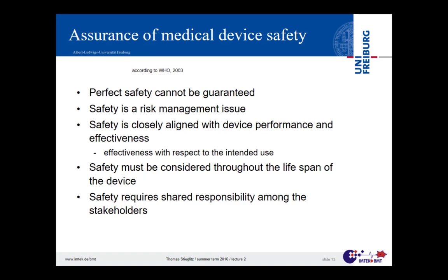can I imagine something where it goes wrong? So failure cause. How often might this occur? How serious is that? And can I detect that? The detection thing has been hidden a little bit, but the occurrence rate and the severity are things that go into the risk management system. And then, of course, you have to decide, can I take measures? Best is from the constructional side to prevent that risk. And this always is aligned with the device performance and the effectiveness and the intended use.